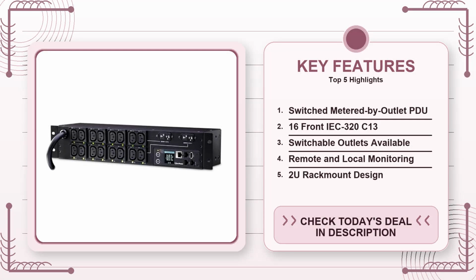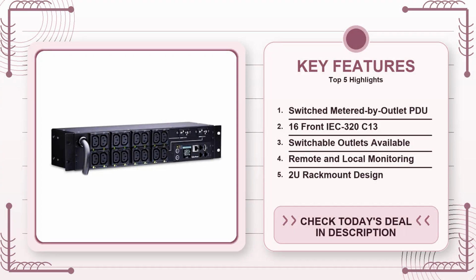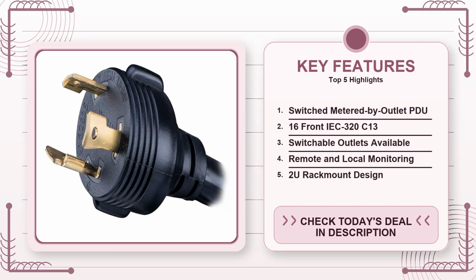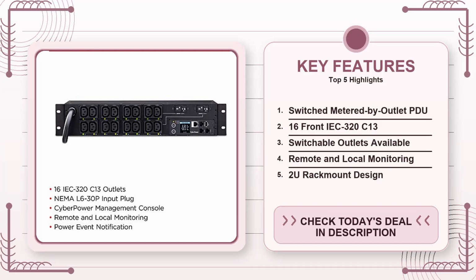The PDU is a 2U rack mount, so it occupies vertical space that could otherwise hold an extra 1U device. The 16 outlets are all on the front, which is great for visibility, no hidden sockets you have to reach around. However, they're all IEC-C13 style, meaning you'll need compatible cords or adapters for equipment that uses IEC-C19 or NEMA plugs.